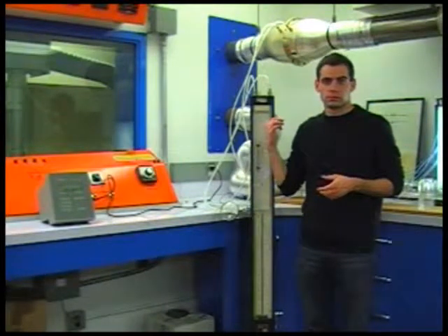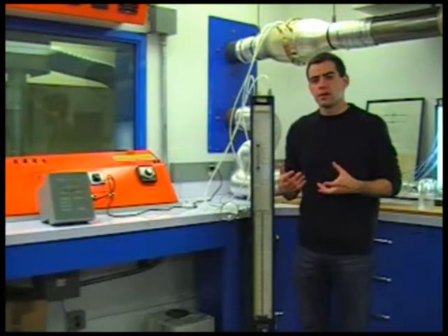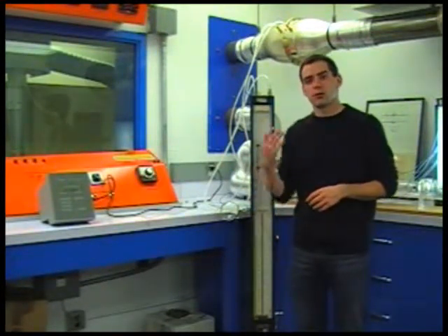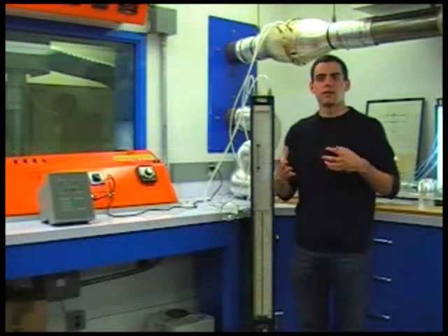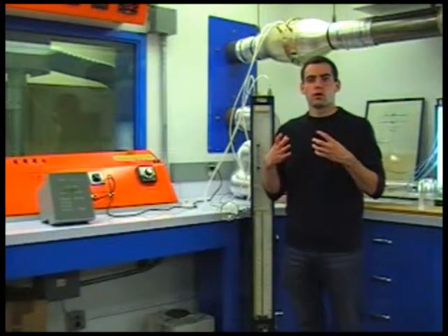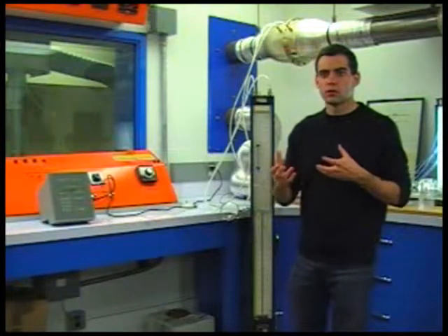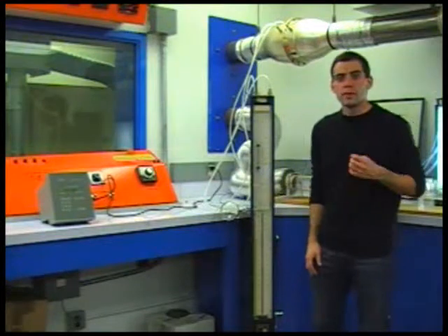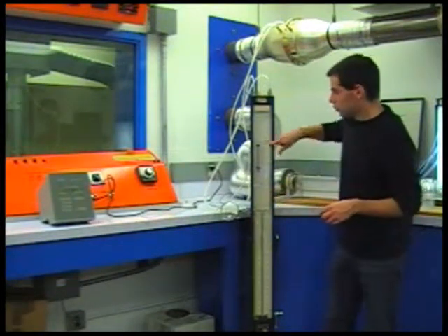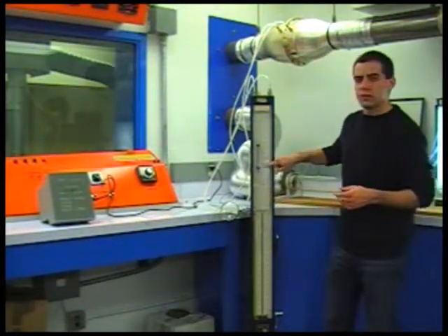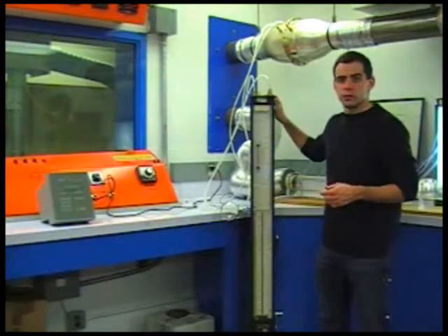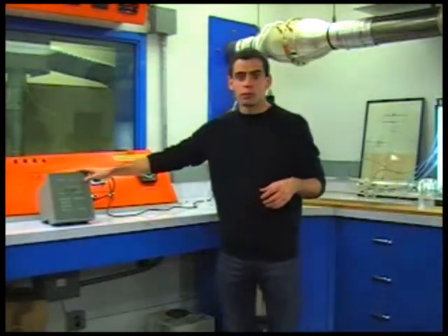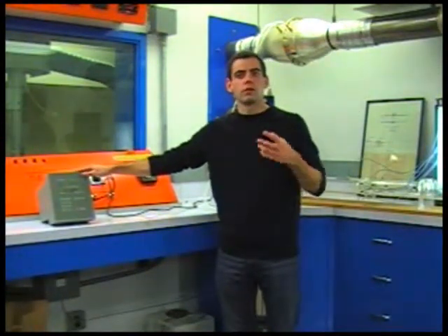bundled tubes. That pressure drop, in addition to depending on the flow rate, also depends on the temperature and the atmospheric pressure, because these change the density of the air. And so you'll have to apply correction factors, which you can find in the manual for the laminar flow element. You should measure temperature in the room using any thermometer. The thermometer, in this case on the manometer connected to the laminar flow element, will work fine. And you should measure atmospheric pressure using the digital pressure gauge, which you used during the pressure measurement lab.